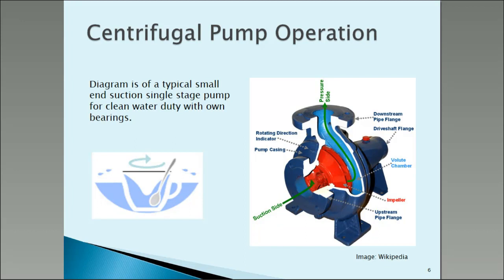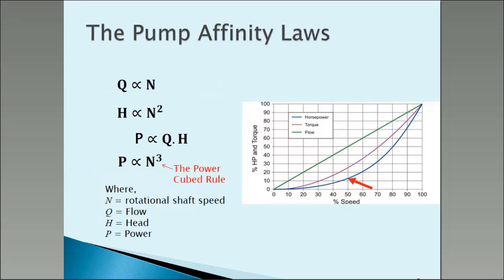A properly engineered pump has the impeller in red. The water goes in on the suction side, which is in green, and then comes out the top on the pressure side. The impeller spins the water around very, very fast, driven usually by a motor. Then the water is thrown out into what's called the volute — the light blue bit — and out the top. The amount of water going in is going to be the same as the amount going out, but the pressure will be greater going out. That is what a pump is.